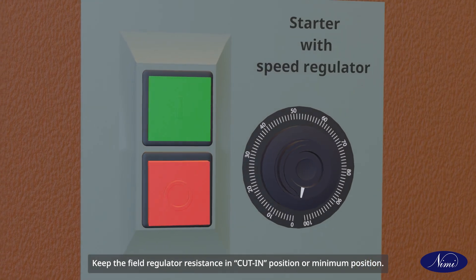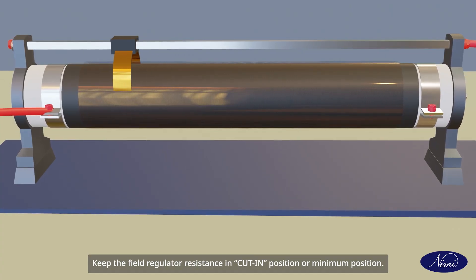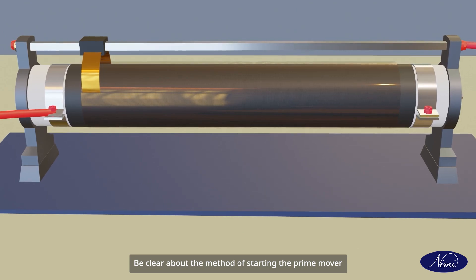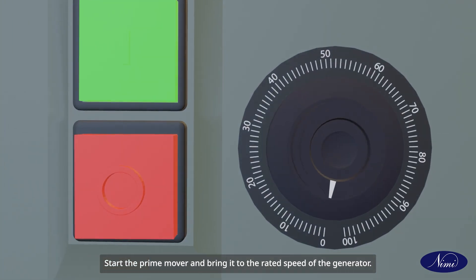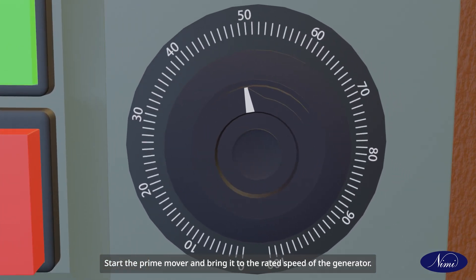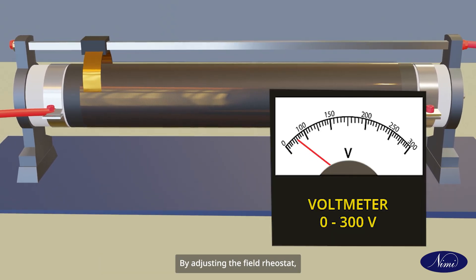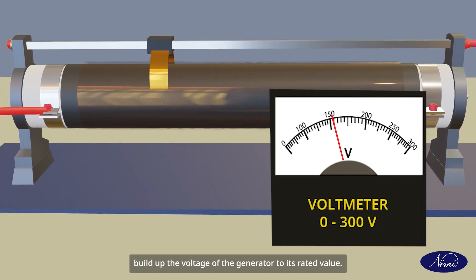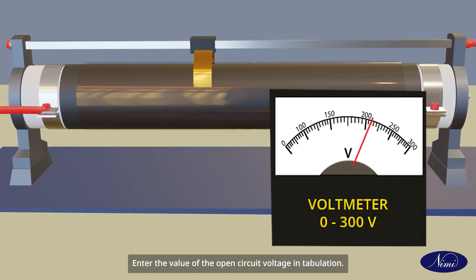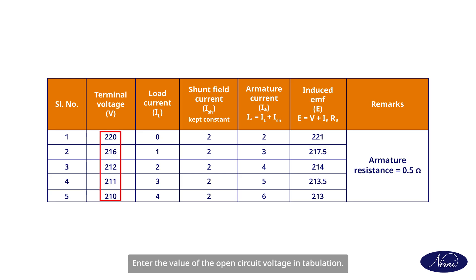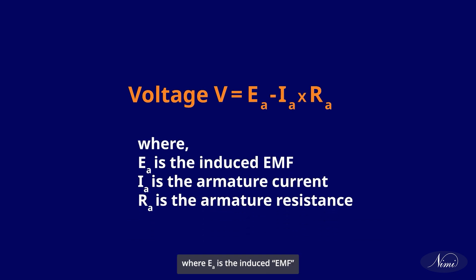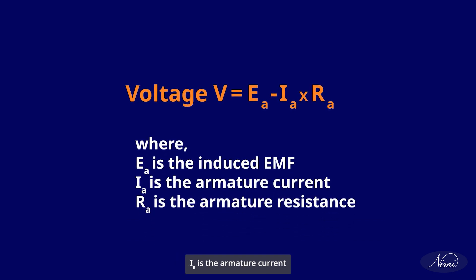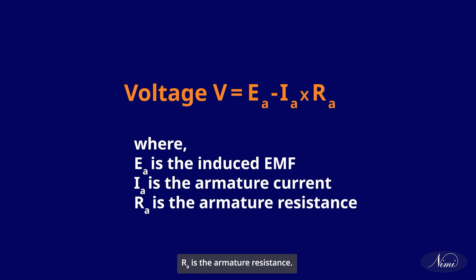Keep the load switch open and switch off all the circuit switches in the lamp load. Keep the field regulator resistance in cut-in position or minimum position. Be clear about the method of starting the prime mover and the procedure of adjusting its speed. Start the prime mover and bring it to the rated speed of the generator. By adjusting the field rheostat, build up the voltage of the generator to its rated value. Enter the value of the open circuit voltage in tabulation. Determine open circuit voltage: V = E − (Ia × Ra), where E is the induced EMF, Ia is the armature current, and Ra is the armature resistance.